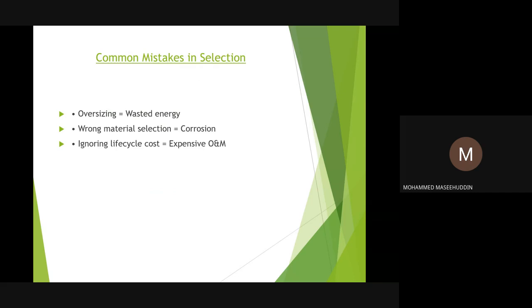Okay, common mistakes we normally make in selections: oversizing. As we have just seen in the last slide, even though we could have easily taken a 37 kilowatt motor, because it is selected on 30, no, since the absorbed power is only 24, we don't need to go for the higher rating of motor. Then the wrong selection of material itself. As I told you, we can use either a cast iron casing or a stainless steel casing or anything, but it really depends on the type of water being used in the building. The type of water means the conductivity of the water itself. Then ignoring the life cycle cost, expensive operation and maintenance, of course.